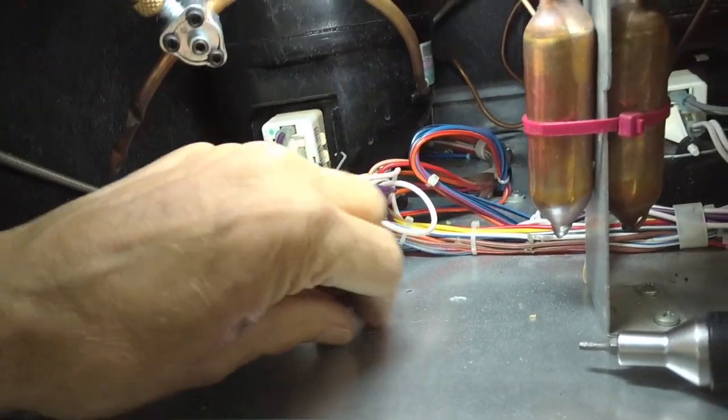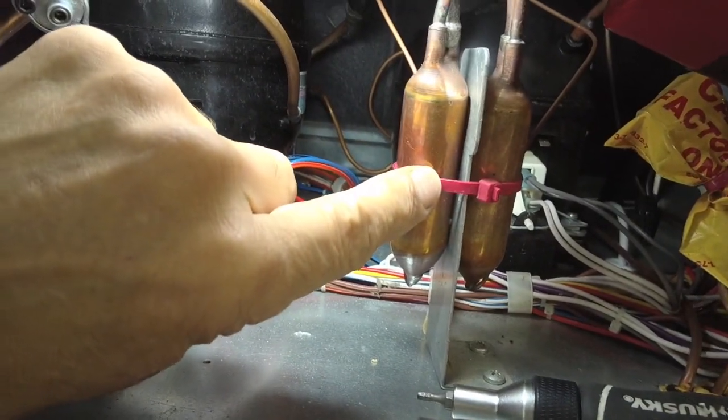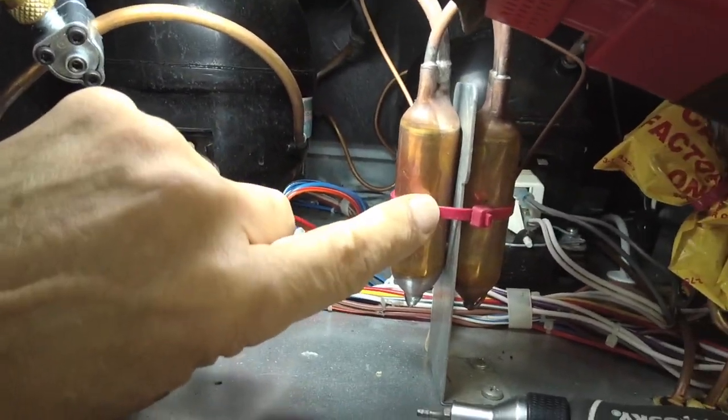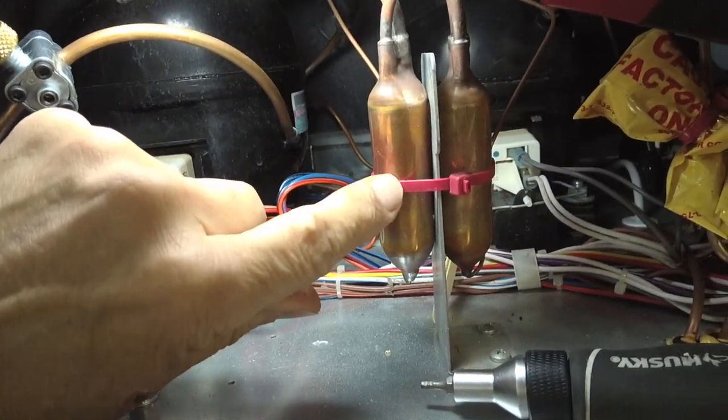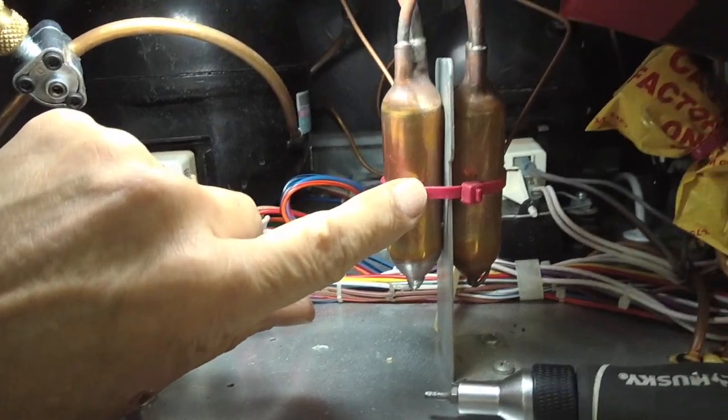After we've taken all the freon out, we're going to cut this dryer out and put a new dryer in here because it's recommended that whenever you go into the sealed system, you replace the dryer. So that'll be our next step.